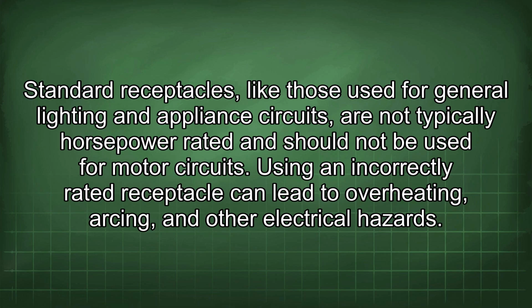Standard receptacles, like those used for general lighting and appliance circuits, are not typically horsepower rated and should not be used for motor circuits. Using an incorrectly rated receptacle can lead to overheating, arcing, and other electrical hazards.